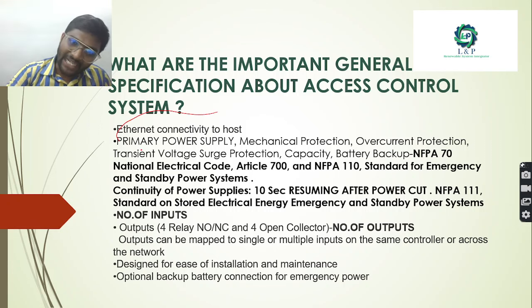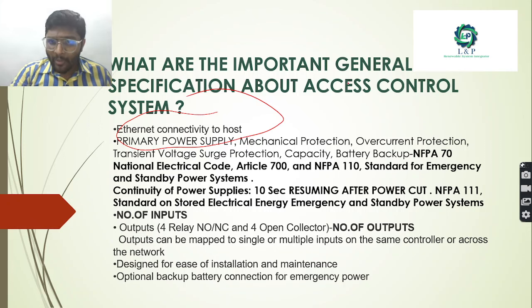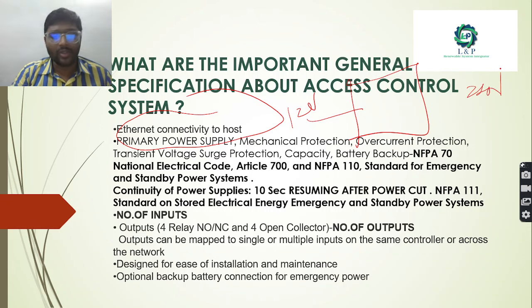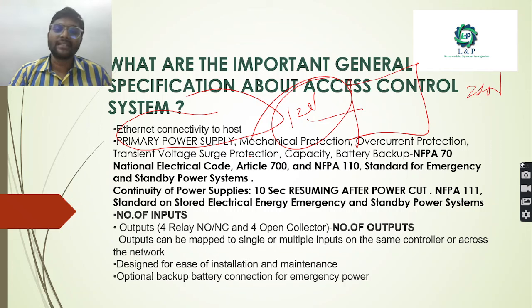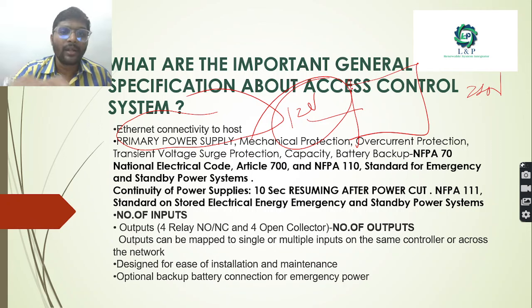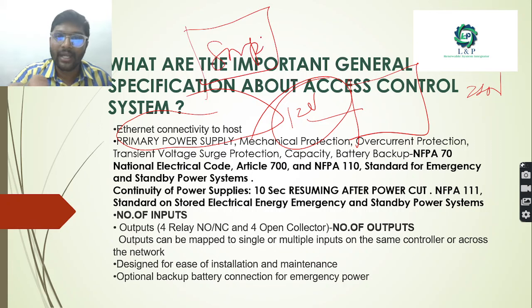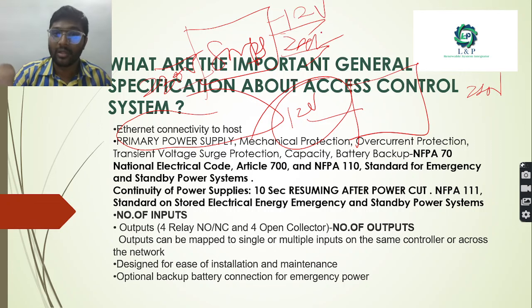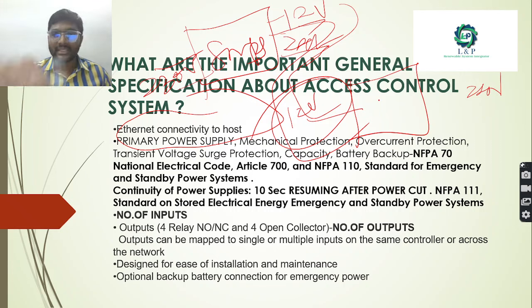Important specifications of an access control system include Ethernet connectivity. The primary power supply for the access controller can be either 12 volt or 24 volt. Most commonly, 12 volt is used. We use an SMPS connected to 230 volt single-phase supply, converting it to 12 volt DC output which is then connected to the card readers.